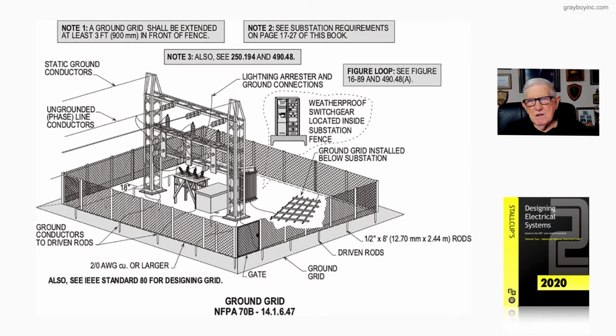Now 70B, the maintenance standard, you would review section 14.1.6.47 for maintenance. But it's that section, they're going to refer you over to IEEE 80, because that's where you get all of your most important rules of maintaining a substation once it's installed, as well as installation rules when you're installing the substation. But keep in mind, this figure 17-37 is strictly dealing now with a customer-owned substation, not a utility substation.